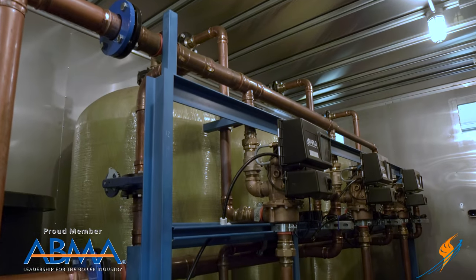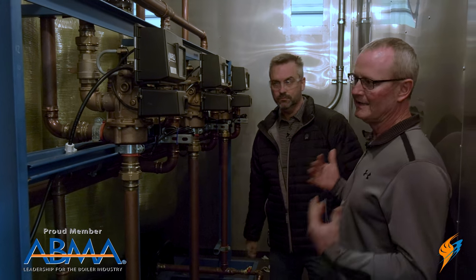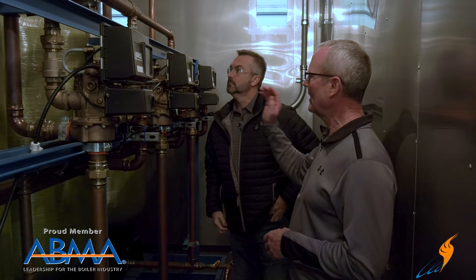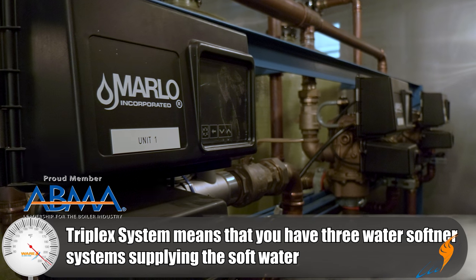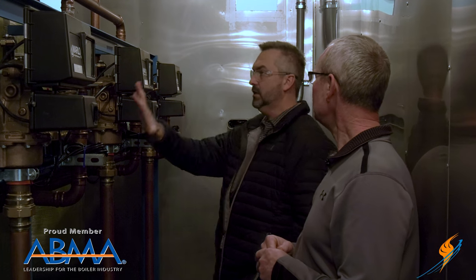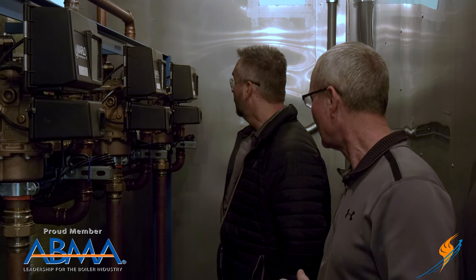We're standing in front of our water softener. This entire system is sized to feed an 82,000 pound per hour boiler. To do that and fit it in this 53-foot trailer, we have to use a triplex system — three resin tanks, with two running at one time while the third is in regeneration, meaning salt water is cycling back through it to get it ready to go back online. We use three because two tanks would be too big and tall to fit in the trailer.